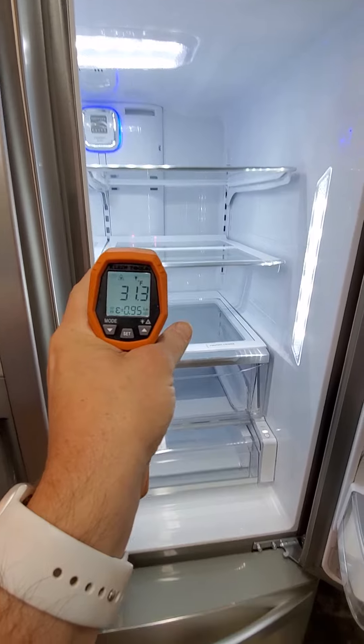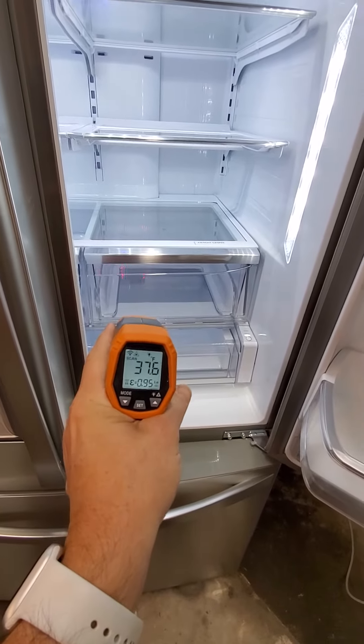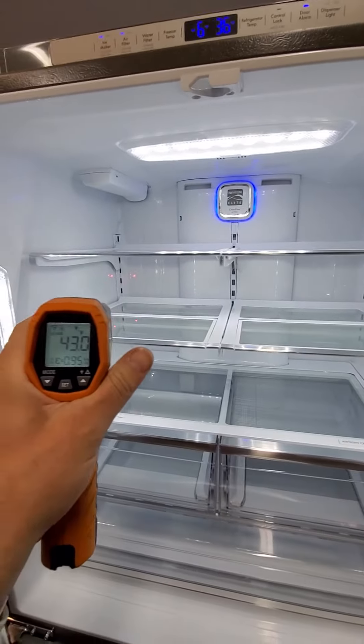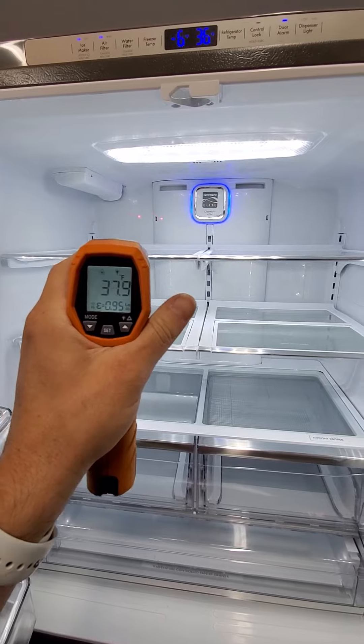So we'll go ahead and open this up. Shoot it right in here. I've also got this set to just about full blast for the fridge. As you can see it's right about — I think I set it to 36 — and the freezer negative six there, but of course as we fan the doors it's going to warm up a little bit, but that's about perfect there.